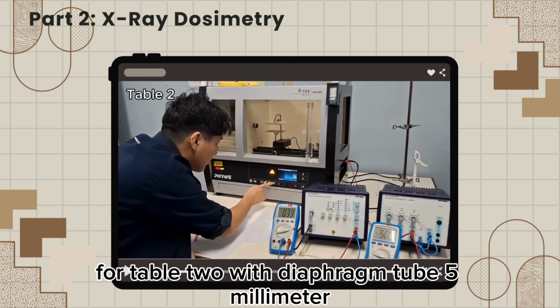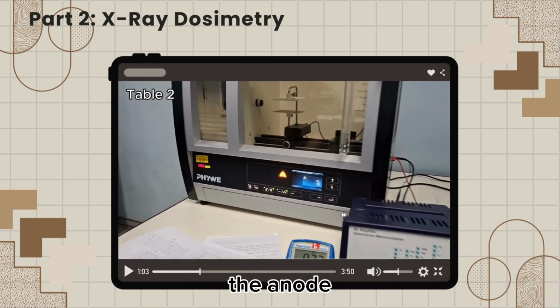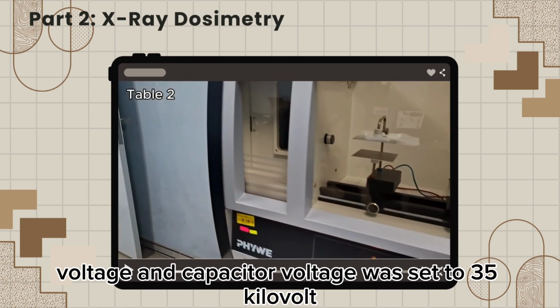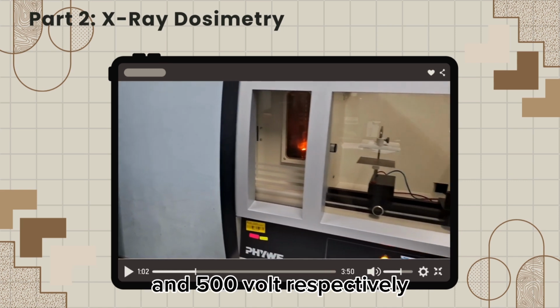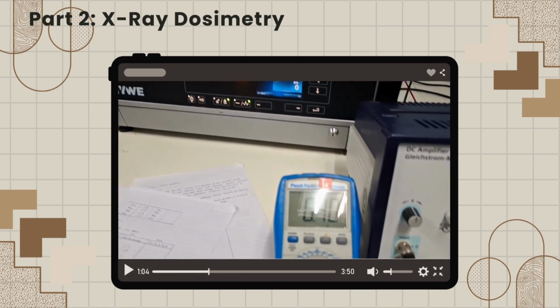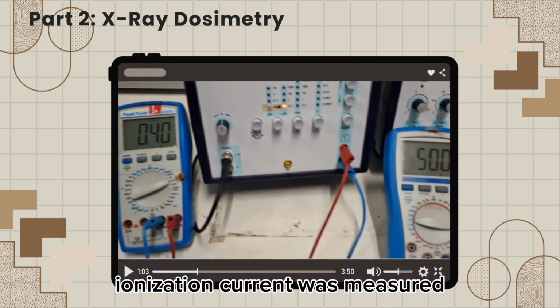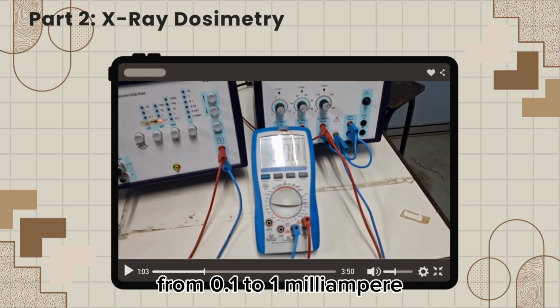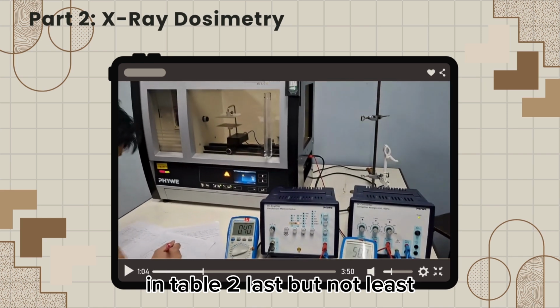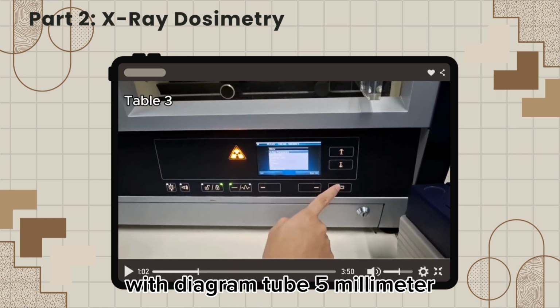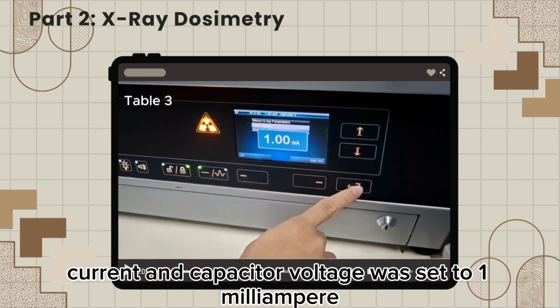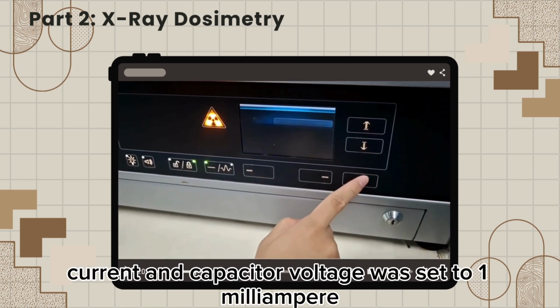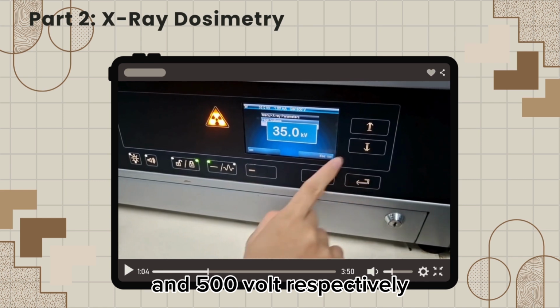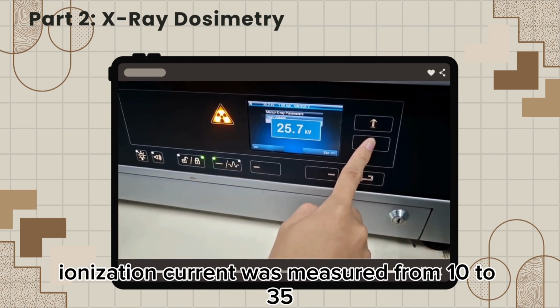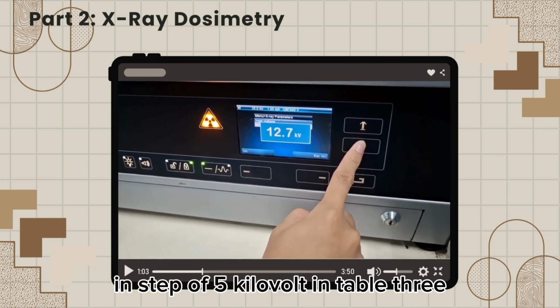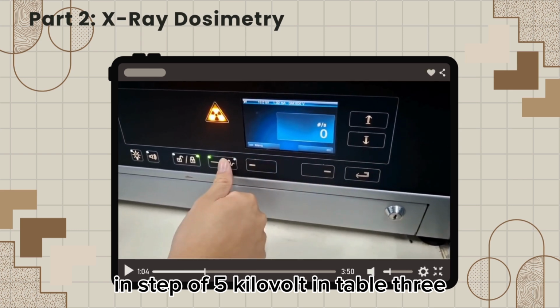For table 2, with diaphragm tube 5 mm, the anode voltage and capacitor voltage were set to 35 kV and 500 V respectively. Ionization current was measured from 0.1 to 1 mA in table 2. Last but not least, with diaphragm tube 5 mm also, the anode current and capacitor voltage were set to 1 mA and 500 V respectively. Ionization current was measured from 10 to 35 kV in steps of 5 kV in table 3.